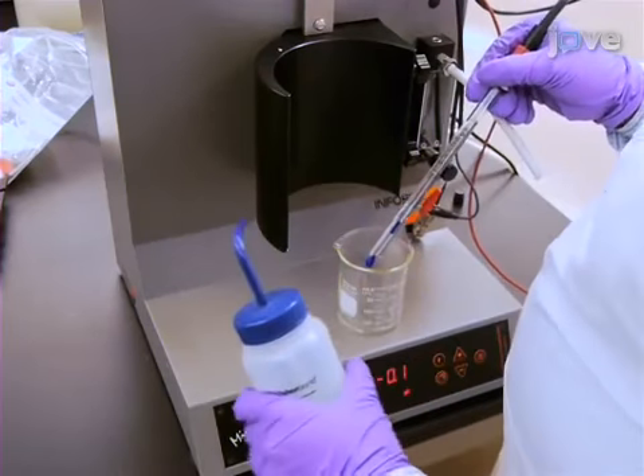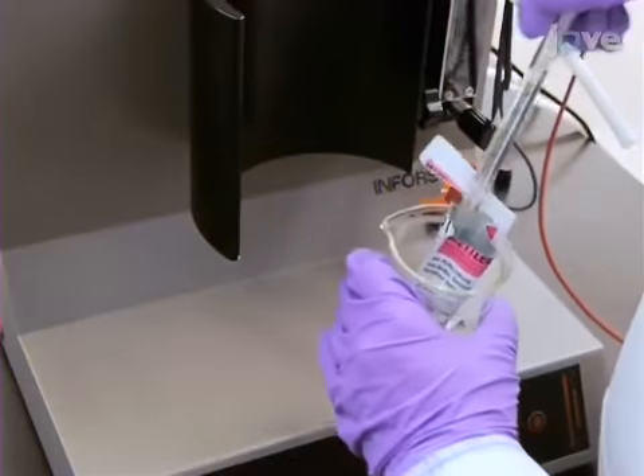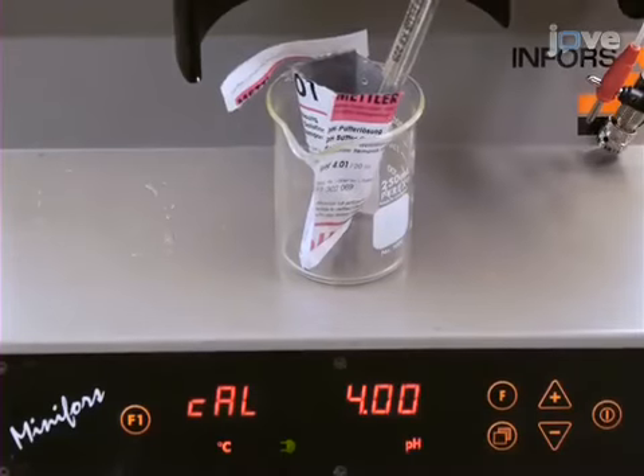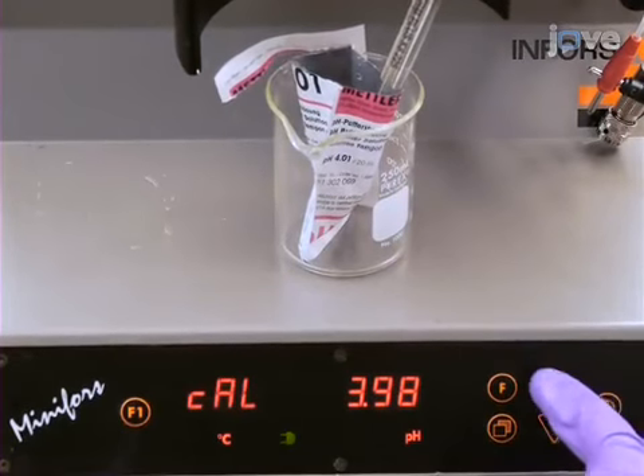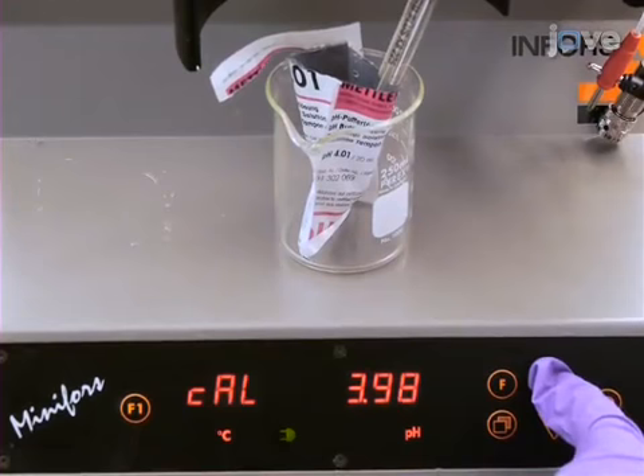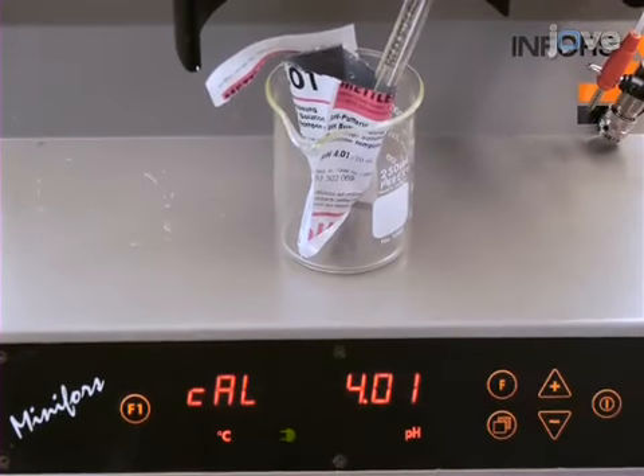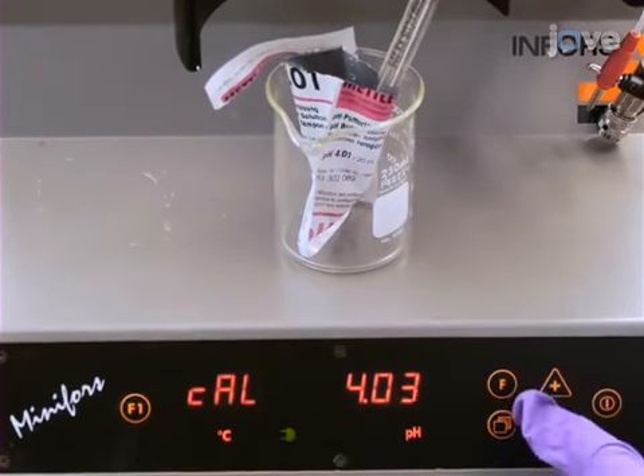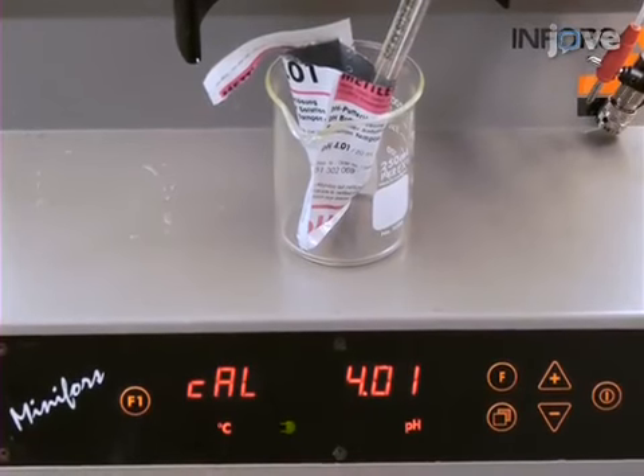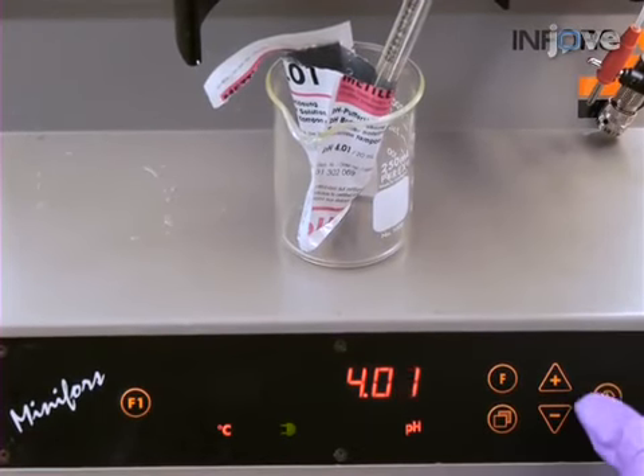Wash the pH probe tip and submerge it in the low reference buffer. The value on the fermenter will stabilize. Using the plus and minus keys, adjust the displayed value to match the value of the pH reference buffer. Once it stops blinking, press Enter.